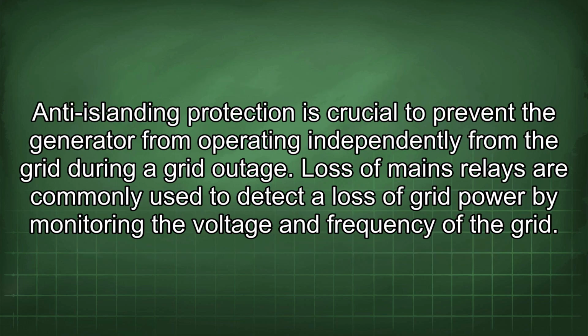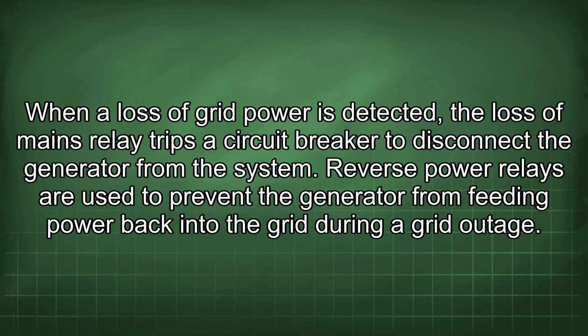Anti-islanding protection is crucial to prevent the generator from operating independently from the grid during a grid outage. Loss of mains relays are commonly used to detect a loss of grid power by monitoring the voltage and frequency of the grid. When a loss of grid power is detected, the loss of mains relay trips a circuit breaker to disconnect the generator from the system.